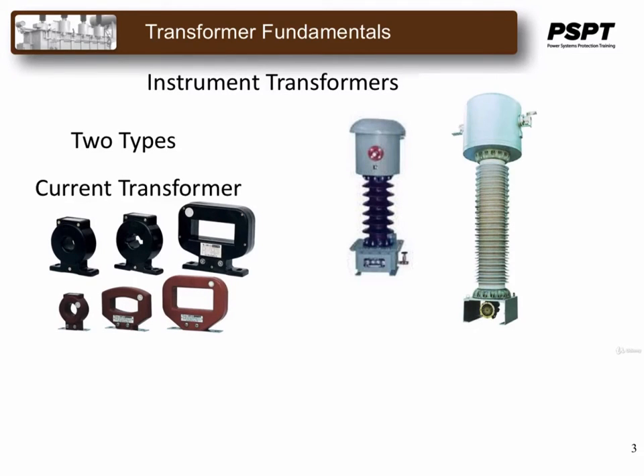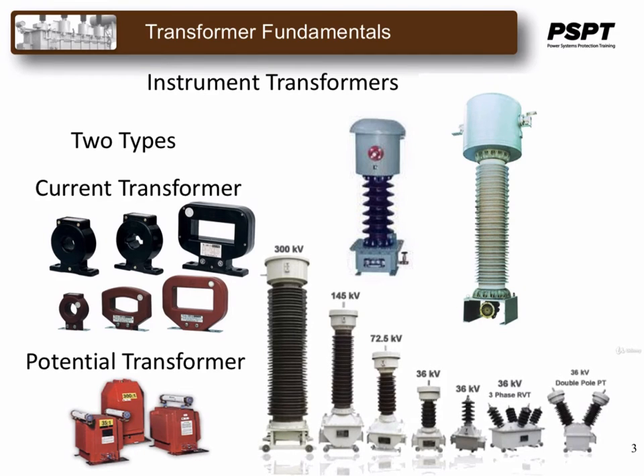Current transformers are used when the magnitude of AC current exceeds the safe value of the current required for the measuring instruments. Potential transformers or voltage transformers are used where the voltage of the AC circuit exceeds 750 volts and it is not possible to provide adequate insulation on measuring instruments for voltage more than this.